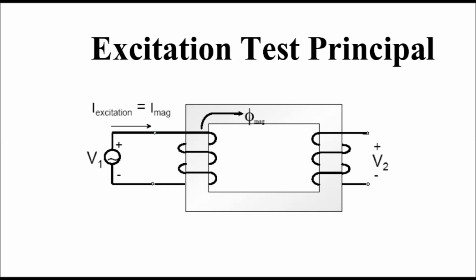Excitation test principle. The excitation test principle for a single phase power transformer has been shown in this diagram. Here, single phase supply is given to the primary side of the winding and the secondary side winding remains open. Due to the supply given on the primary side, a current will flow in the primary side. Due to this current, a flux will flow in the direction shown in this diagram. Due to the flow of flux in the core, a voltage will be induced in the secondary winding. Since this current in the primary winding is only to establish a flux to magnetize the core, this current is called the magnetization current or excitation current.